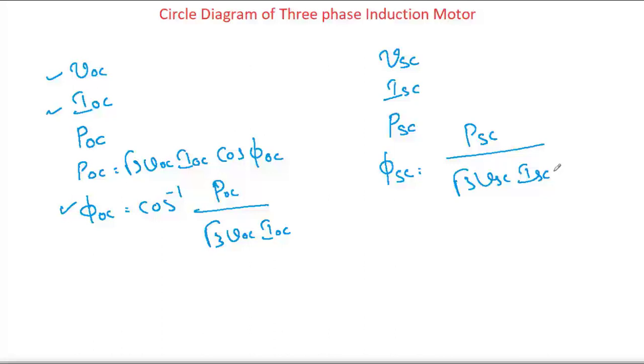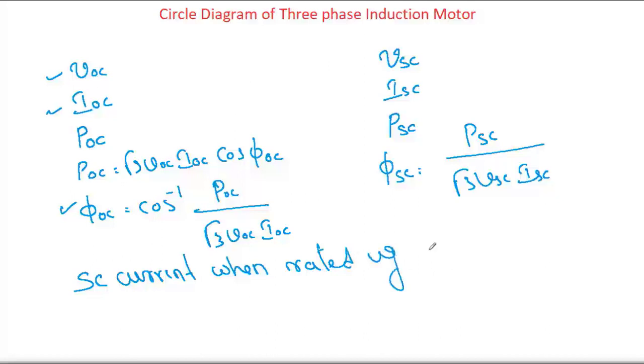Along with that, some other data is also required — the short circuit current when rated voltage is applied. During a block rotor test, we apply not more than 20% of the rated voltage. Theoretically, we need to determine what the block rotor current would be when we apply the rated voltage. Additionally, we should know the values of stator resistance and rotor resistance, which can be obtained by conducting the DC test. With this data, we can go ahead for drawing the circle diagram.